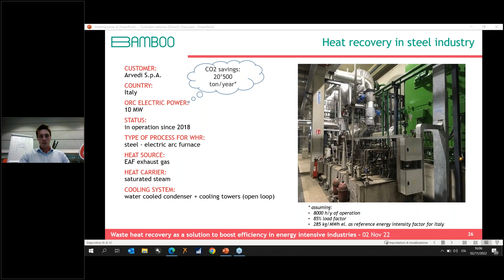the furnace is off. And therefore we have this steam buffer upstream the ORC, which takes the steam during the power on and then delivers part of it to the ORC while keeping the remaining part in the buffer itself in order to use it during the power off. And so this allows the ORC to be less dependent on the variances of the thermal power input, and so the efficiency is more constant during the production of the year.